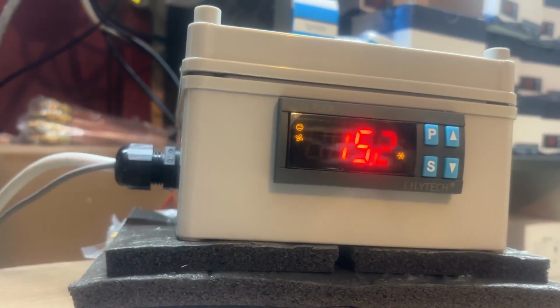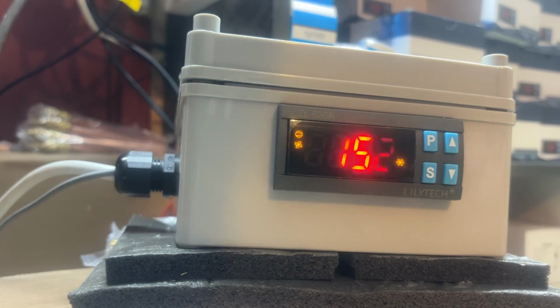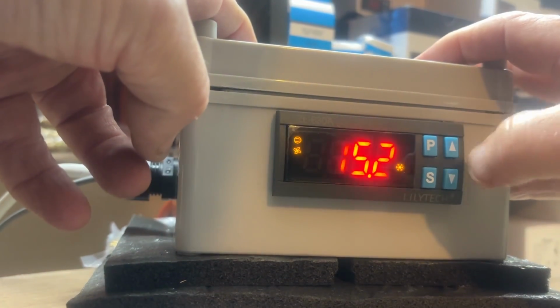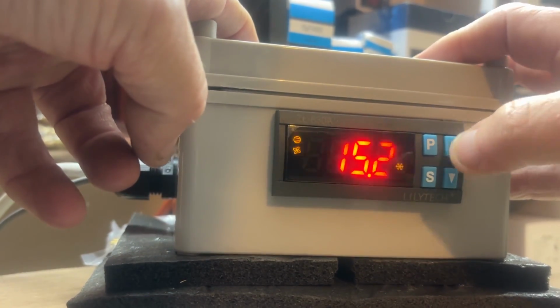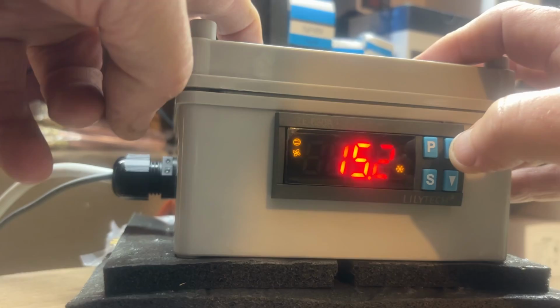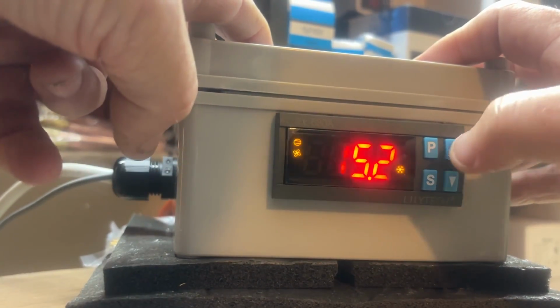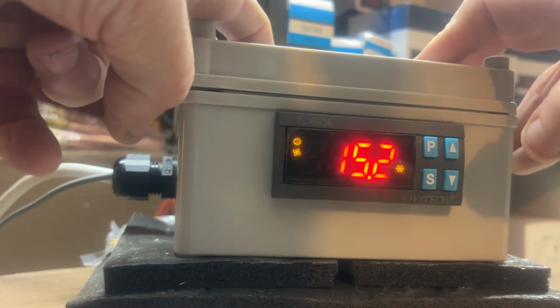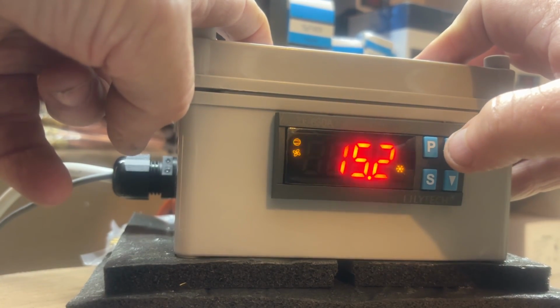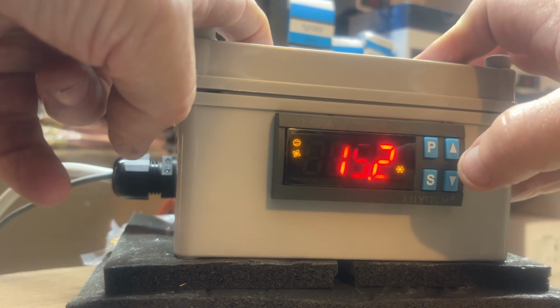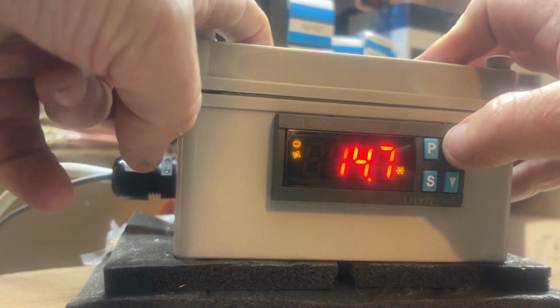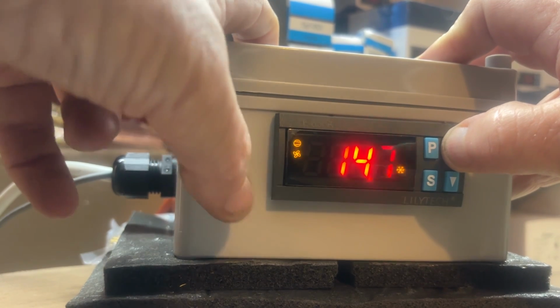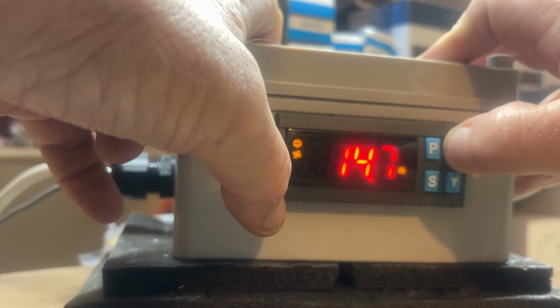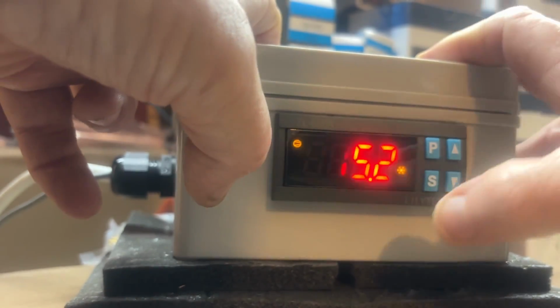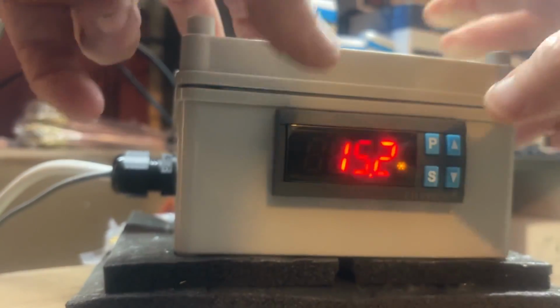Okay, and just getting back to the controller, what I do like about it, to get the defrost sensor temperature, all you've got to do is push that. So the defrost sensor is 14.7, and the ambient or the cabinet sensor is 15.2. They're a little bit different, but quite often sensors are never exactly the same. If you want to put it onto defrost, just hold this top one in. Hold in, and very shortly, see, it's gone on to defrost. Compressor's gone off, and it's gone on to defrost.